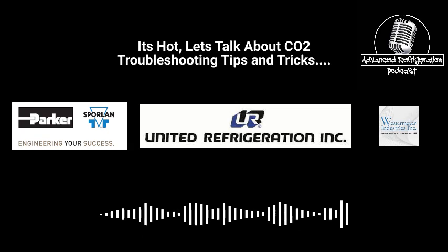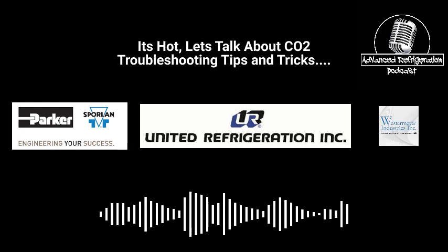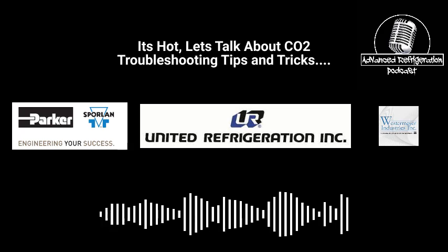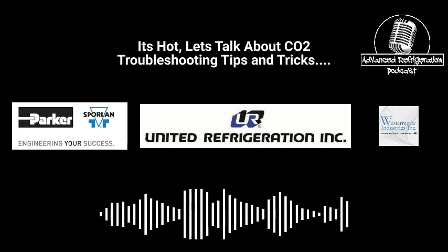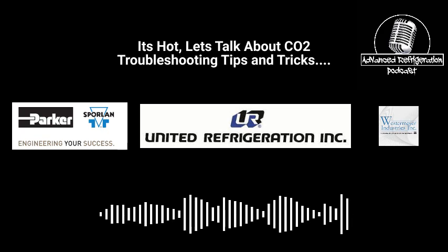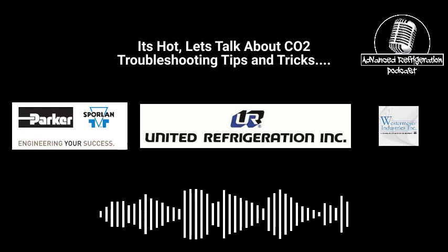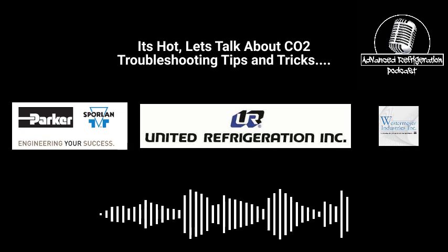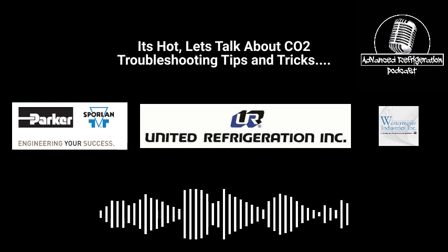They plug up constantly. Before you start saying it's a bad sensor, I would go through and make sure all that's good first, and then check your actual DI operation. Make sure the input is opening and closing, and then actually test it. You can't just take it off there because it's going to fault out. You need an actual glass eye to test it. That's why ordering one when you order a spare to keep in the rack is very important.